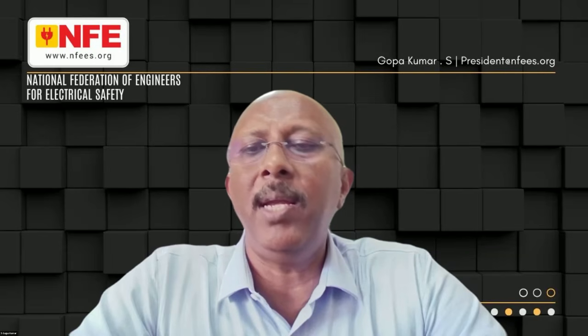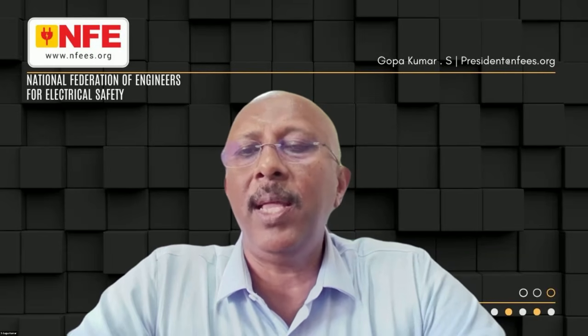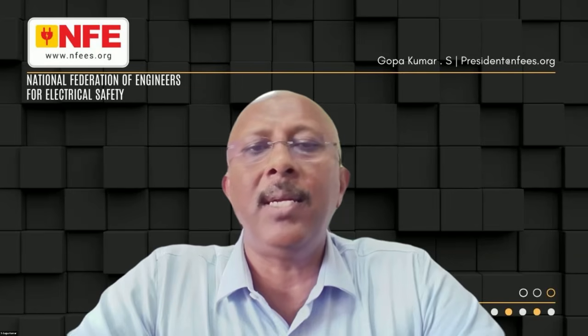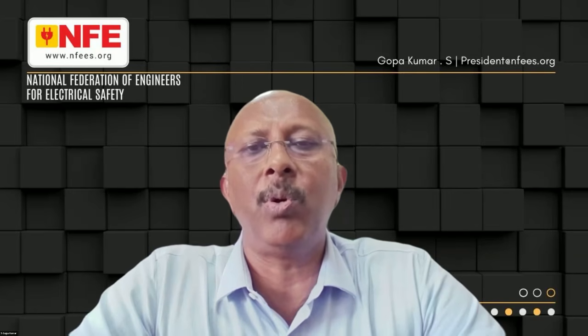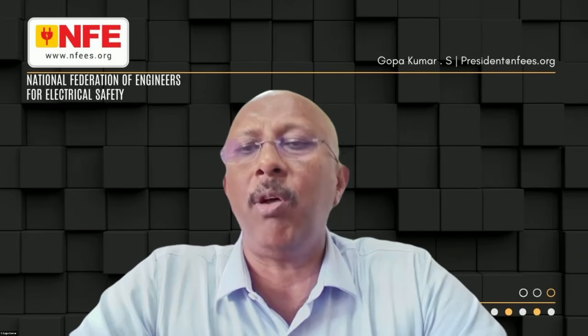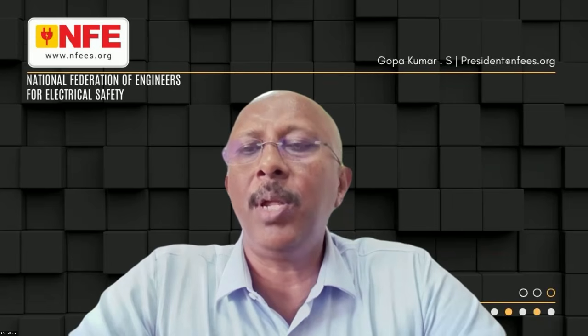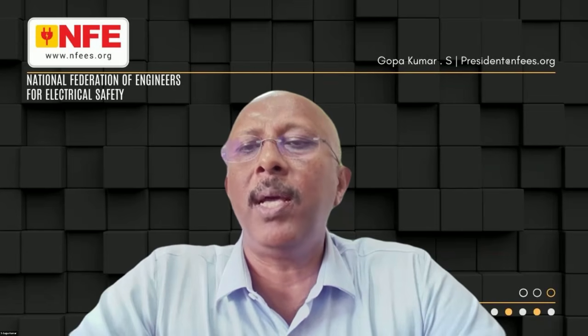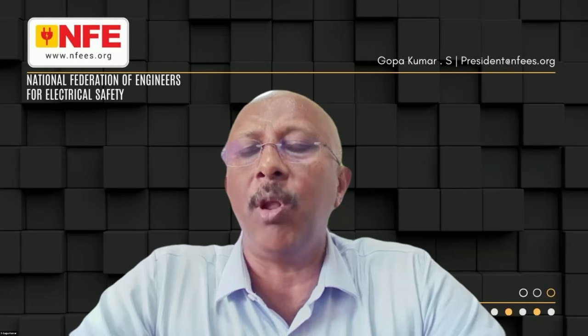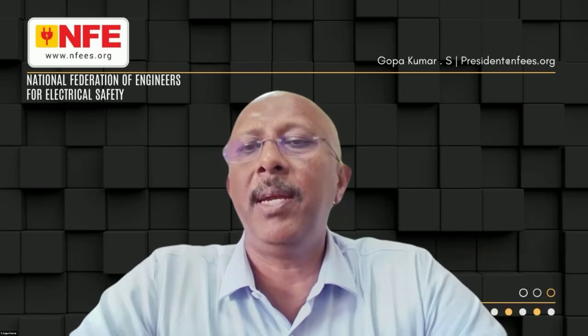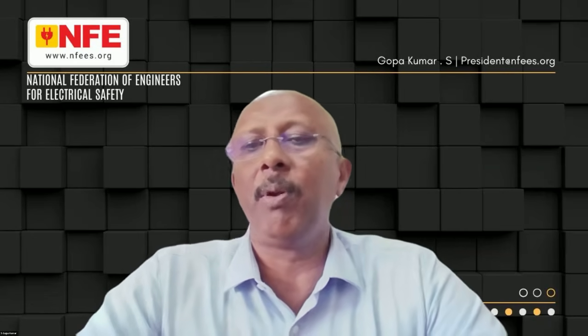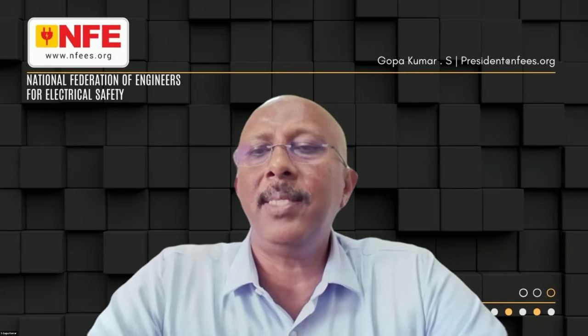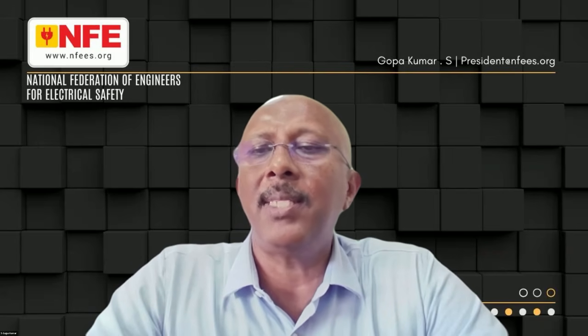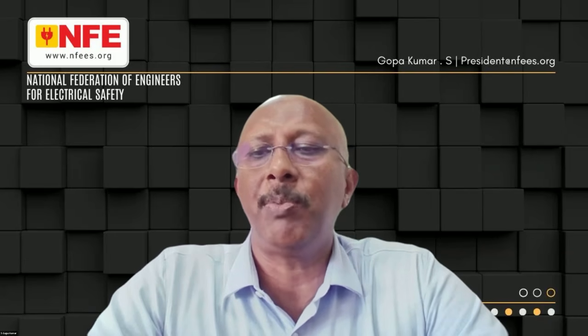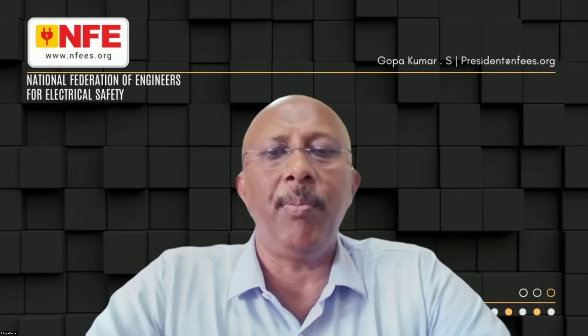Number 2, what the AFDD does is, in case of any arcing, it disconnects the supply. So continuity of supply is lost. Imagine due to an arcing, the power supply to the operation theater is lost. The patient will be in danger. This is the reason AFDD and RCDs are not allowed in Group 2 locations, especially for life-saving equipment.